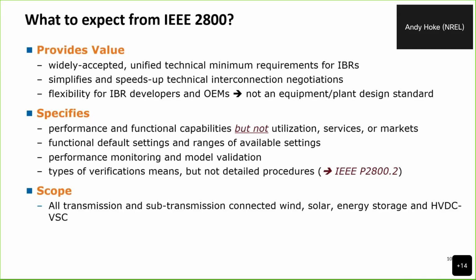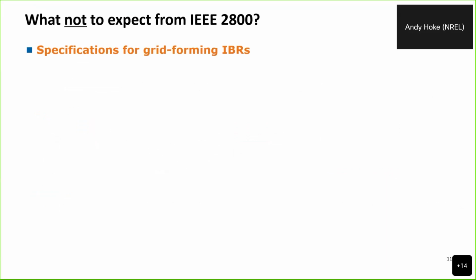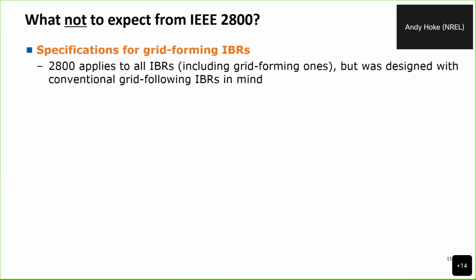I mentioned earlier that it covers all transmission and subtransmission connected wind, solar, battery, and HVDC voltage source converters. And then there's a few things that we don't necessarily expect to get from IEEE 2800. It's not going to go into detail about what to expect from grid forming inverter-based resources, even though those have been sort of a hot topic recently. It does apply to any type of IBR, including a grid forming inverter-based resource.